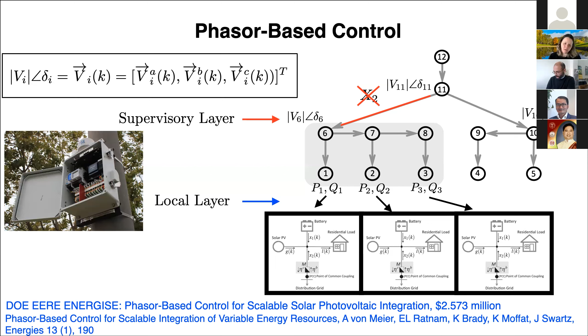Specifically for the supervisory layer, we can set the objective to align phasor targets to drive the power flow across the edge of interest to 0, or we can assign the voltage phasors to balance each phase so the power flow in phases A, B, and C are equal. Our constraints are again the power flow constraints, the voltage constraints, and the battery constraints.